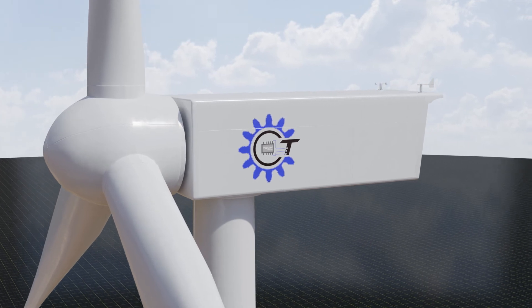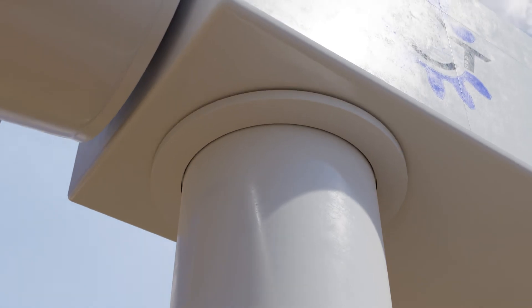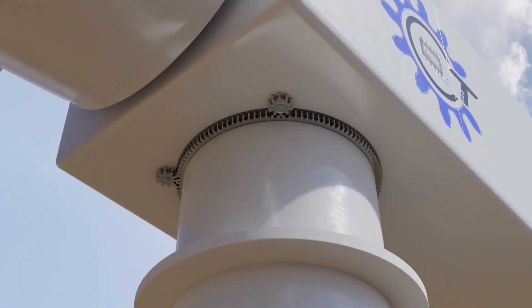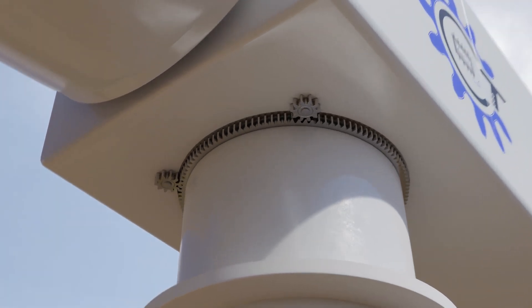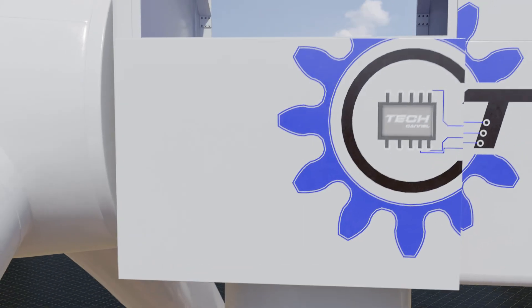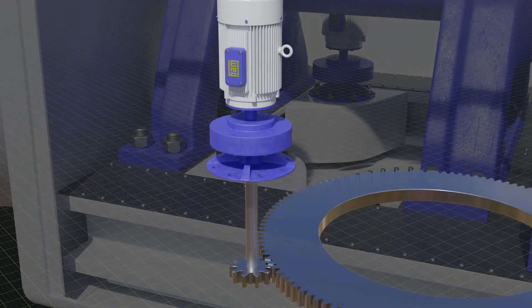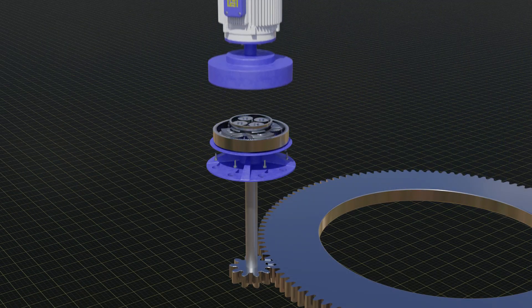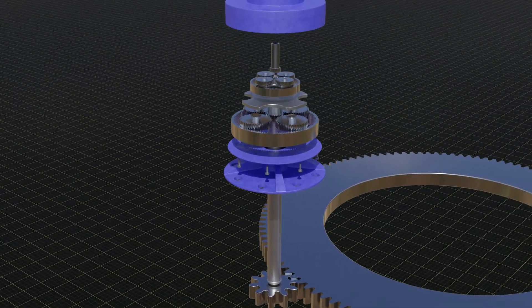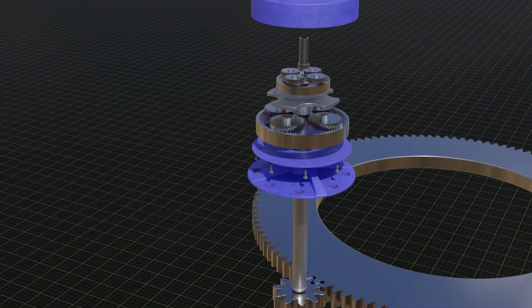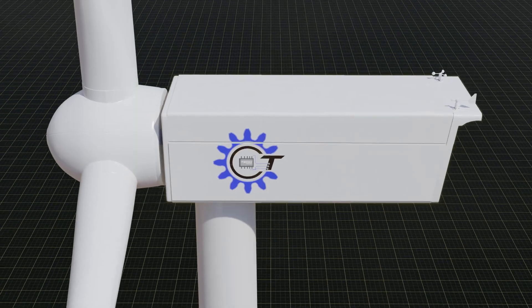A nacelle is installed at the very top of the tower. It is attached to the tower through a ring that can rotate around its axis. To rotate the nacelle, there are several electric motors that rotate the entire nacelle relative to the tower. These motors have a small gearbox which, using a set of gears, turns a fast low-force rotation into a slow high-force rotation. Thanks to this gearbox, these small engines can easily rotate a multi-ton nacelle.